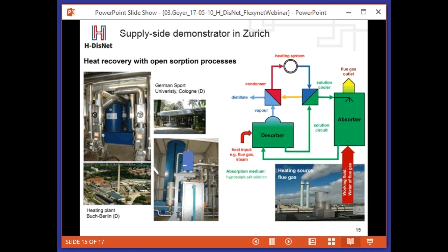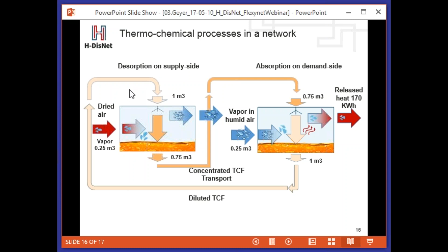We have diluted desiccant coming in for the regeneration. We have air, and hot air removes the humidity from the desiccant, so one cubic meter comes in, we remove the air, and 0.25 cubic meters of water are removed as vapor. 0.75 cubic meters of concentrated fluid goes through the network and is available on the demand side, where absorption takes place. Vapor from other processes comes in, absorption provides heat, and the diluted desiccant goes back again to the supply side.